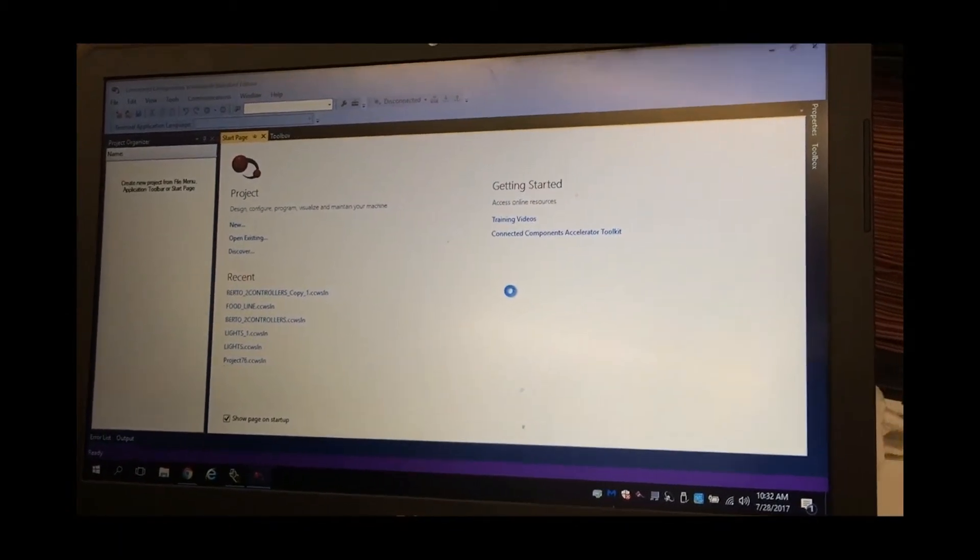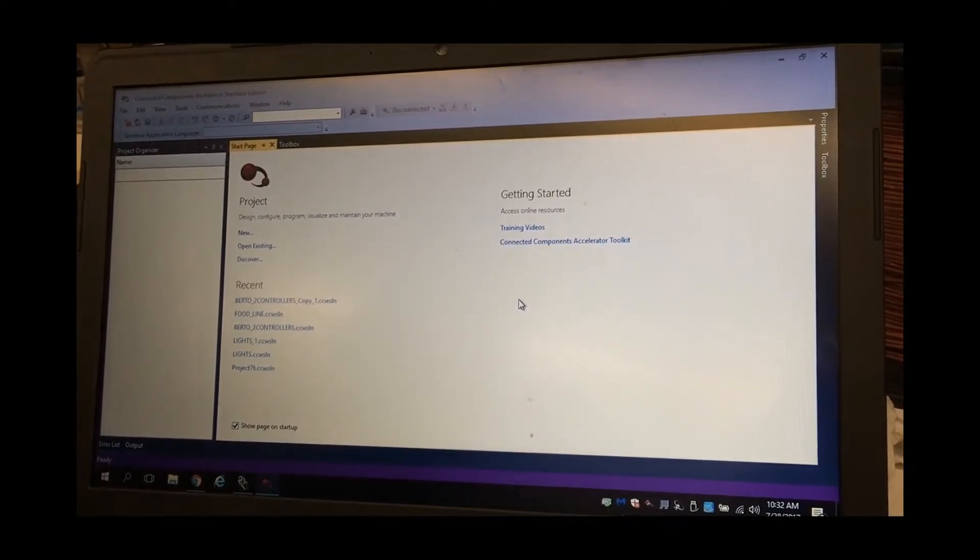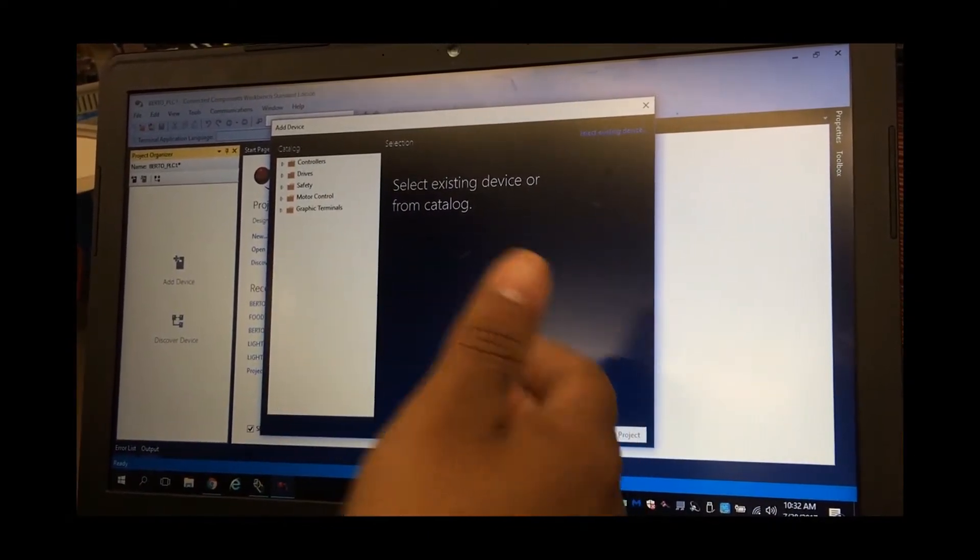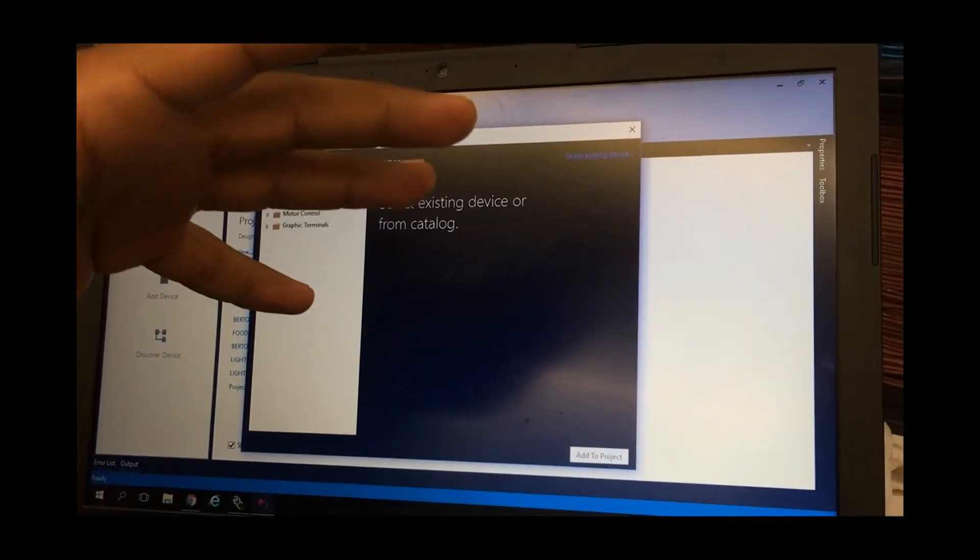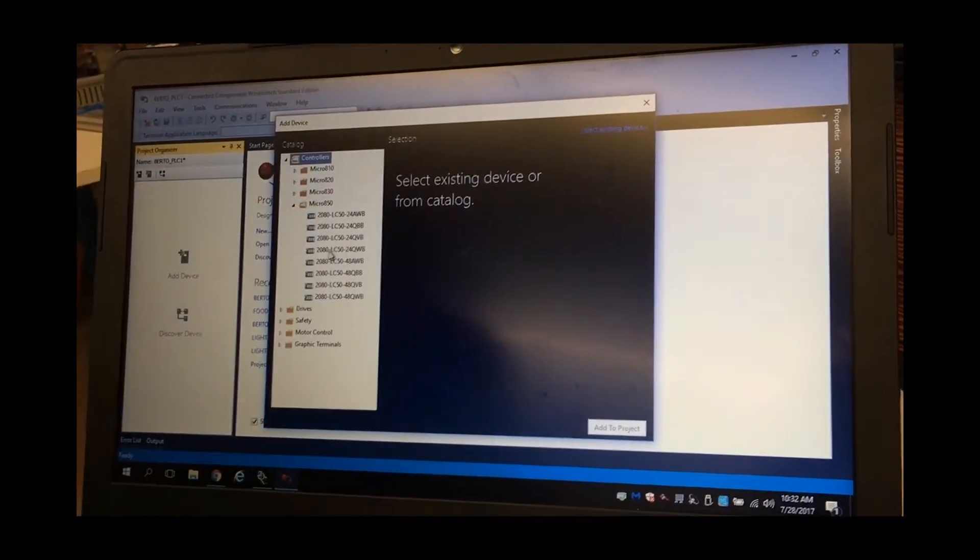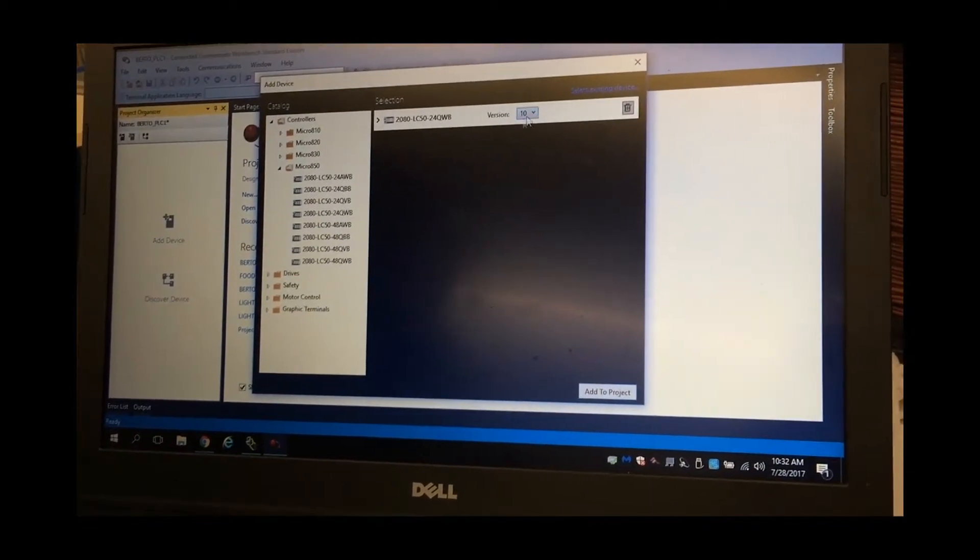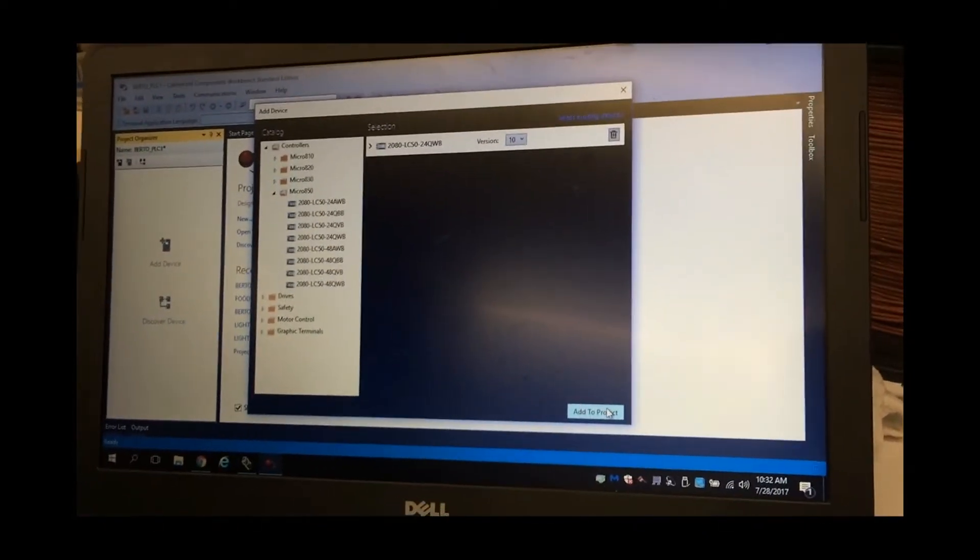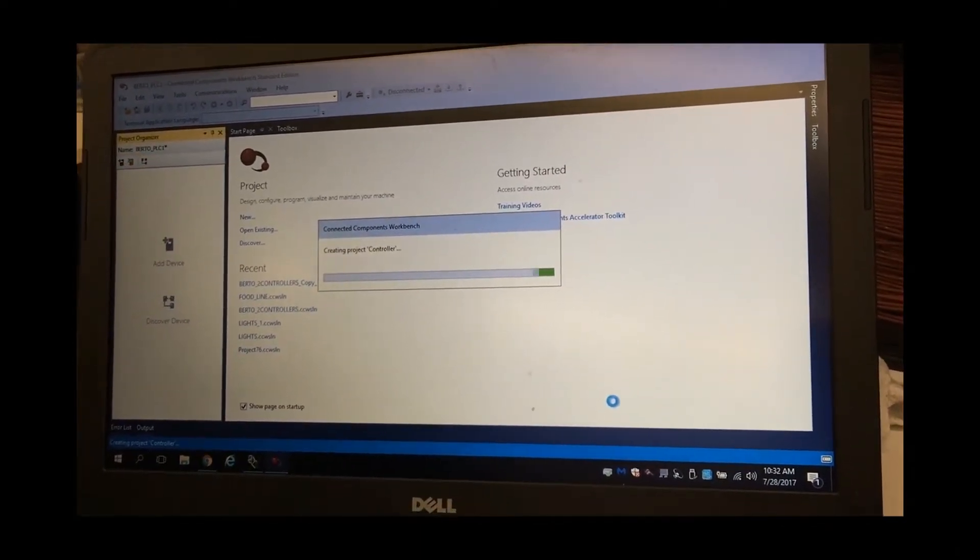Now we're on this and adding devices. We've got to understand what type of controller we're using, what family tree, and here you can add PanelView terminals. But first, we're going to add our controller. We're going to go to Micro850. And we're going to use a 2080LC5024QWB. That's the controller type we have. And you're going to add one, and as you can see, this says version. I just upgraded the version 10 firmware, so you have to put the right version on it. So now we're going to add to project. And it's going to pop up right here on the left side, called the project organizer.